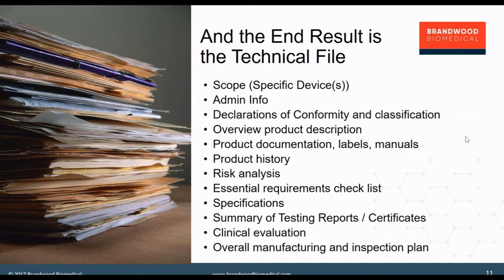Product history, we've talked about that. So, where the product has been released, what's the current compliance state of the product, but also your history of changes as it relates to the essential requirements. The risk analysis is also a very significant piece of evidence to be included in your technical file, mostly because this is actually the primary justification for the verification program that you followed for the product.